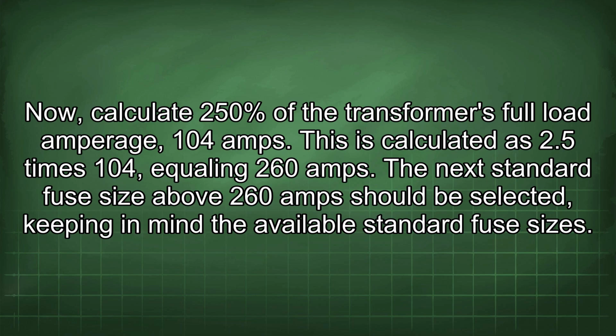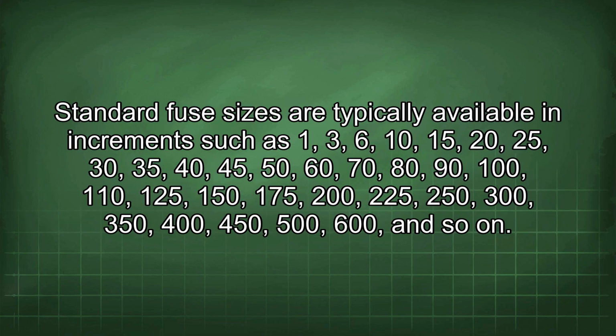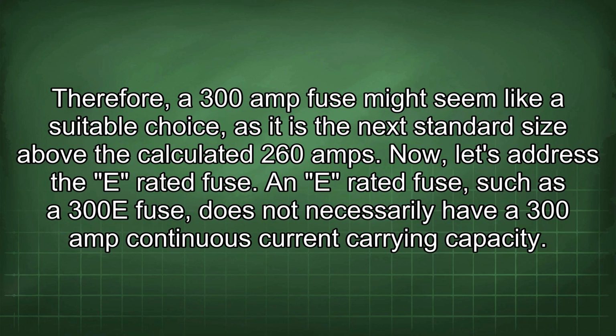The next standard fuse size above 260 amps should be selected, keeping in mind the available standard fuse sizes. Standard fuse sizes are typically available in increments such as 1, 3, 6, 10, 15, 20, 25, 30, 35, 40, 45, 50, 60, 70, 80, 90, 100, 110, 125, 150, 175, 200, 225, 250, 300, 350, 400, 450, 500, 600, and so on. Therefore, a 300 amp fuse might seem like a suitable choice, as it is the next standard size above the calculated 260 amps.